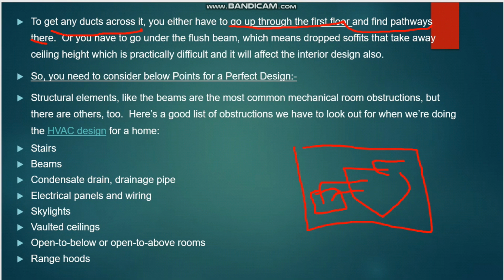Because for the mechanical engineer it is very important. From the architectural point of view, they have given us a room, that's all. Otherwise you have to go under the flush beam, which means dropped soffits that take away the ceiling height, which is practically very difficult, and it will also affect the interior design. So the second case is not possible. Only the first case you have to follow. You have to go through the first floor, and again take it down to the ground floor.